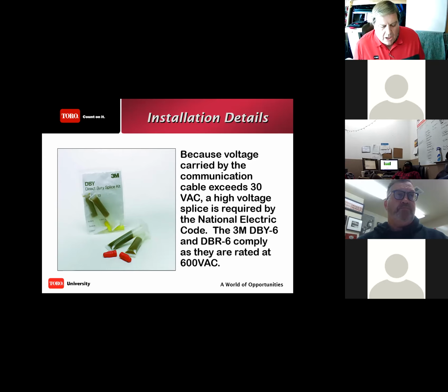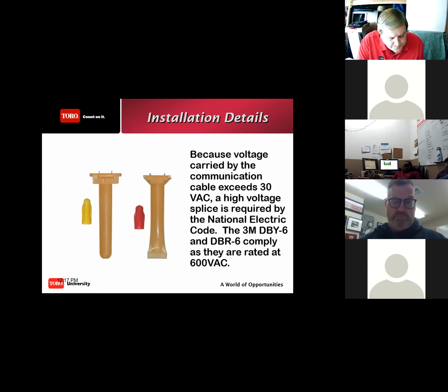Second, many of the 2-wire systems use 30, 40, up to 50 volts on that 2-wire path. It's a 24-volt style system, but with the wire connections, you can't just use a standard, average, everyday, run-of-the-mill wire connection. You have to use one that's designed specifically for 2-wire. We'll get into that a little bit more.